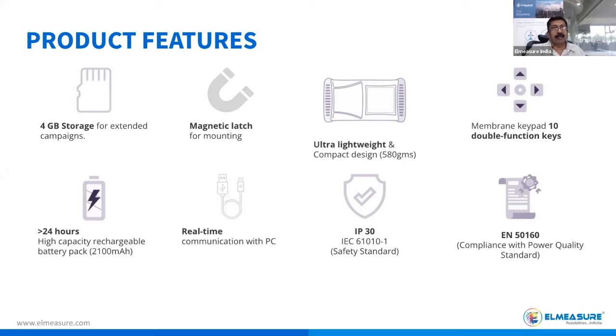Coming back to one good feature in this product, it has got a magnetic latch at the bottom. There are 4 magnetic latches provided. You can fix it wherever there's a magnetic acceptable thing like iron or anything, you can just fix it there. It will immediately catch hold of that and you can do the measurement, which means one person can be used to do the measurement. No need of 2 people, one to hold the meter and the other to connect the probes. It's not required in this. You can just straight away use the magnetic latch to fix it on the panel and do the measurements.